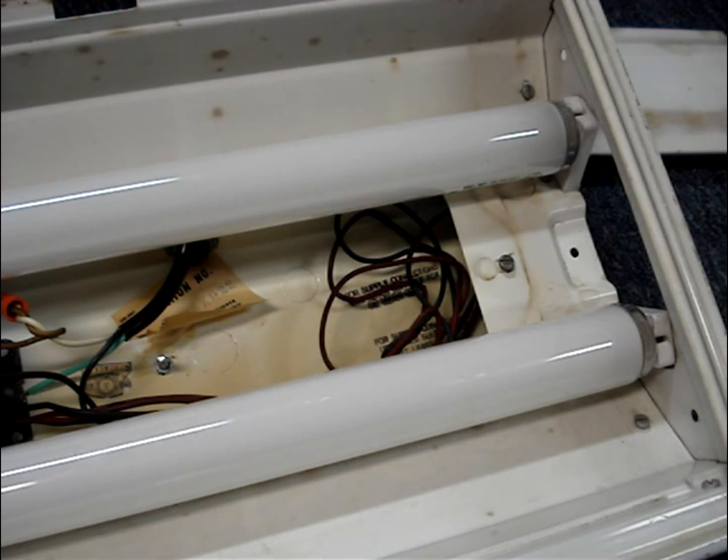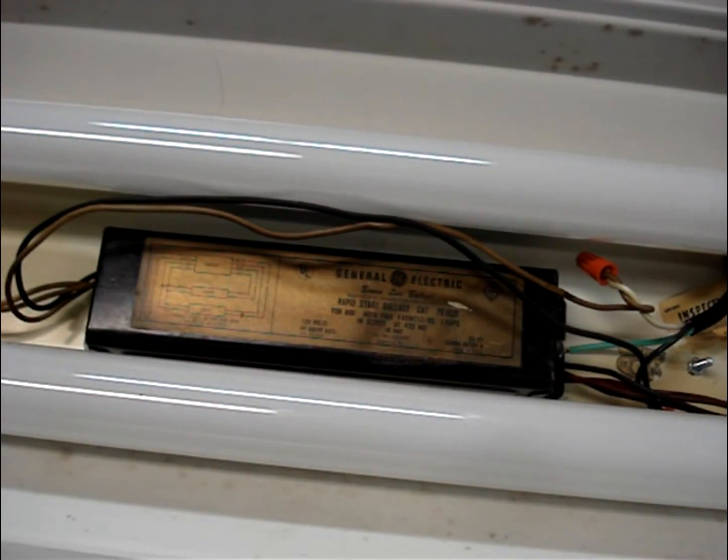When the light is turned on, the ballast sends an AC voltage spike to the ends of the tubes. After the inert gases inside of the tubes arc, then the job of the ballast is to regulate the AC voltage to keep the lights lit. Four different types of ballasts are common and some are wired in parallel and some are wired in series.